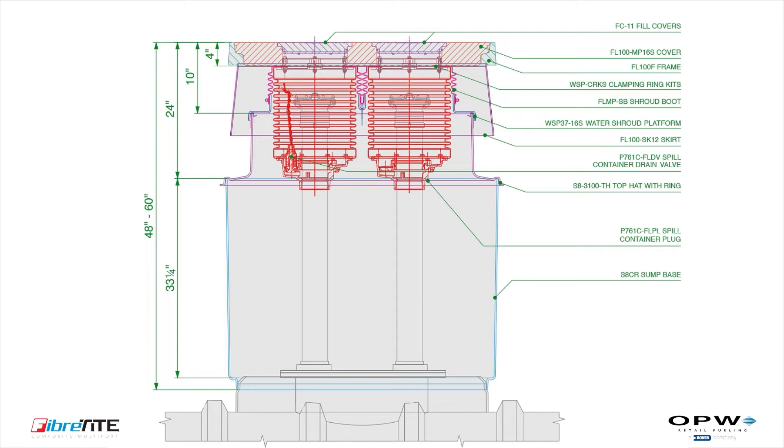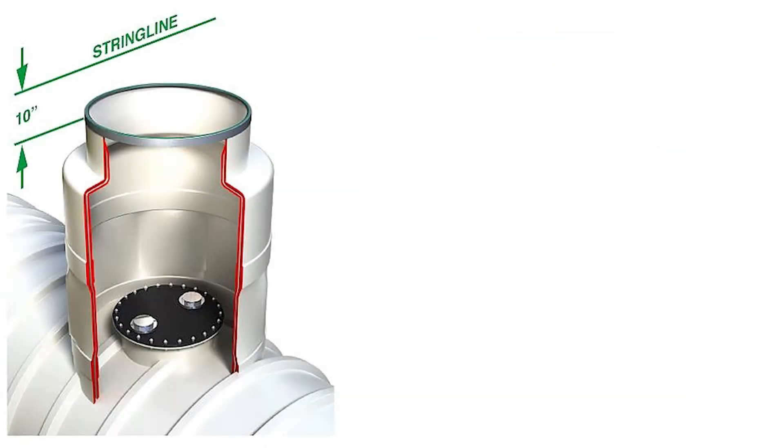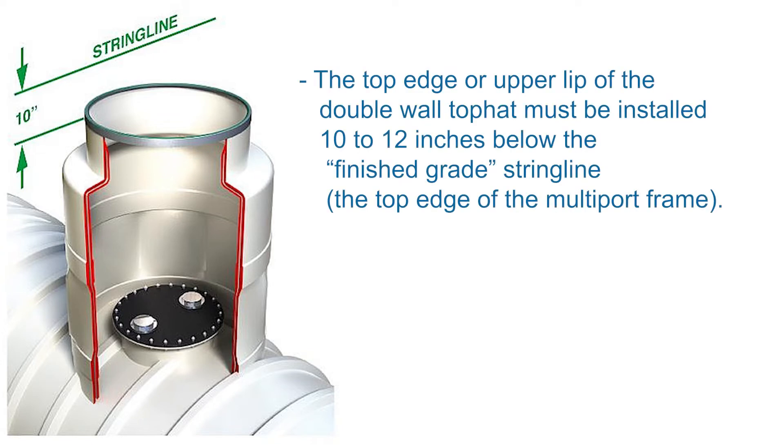Please contact OPW Technical Support if you have any questions or concerns during installation. For the FibreTITE multiport kit for double-wall sumps, the top edge or upper lip of the double-wall top hat must be installed 10 to 12 inches below the finished grade string line, defined as the top edge of the multi-port frame. Installing the double-wall tank sump too high or too low may cause issues with the installation. Now let's join Jim Goodman as he demonstrates how the multi-port should be installed.